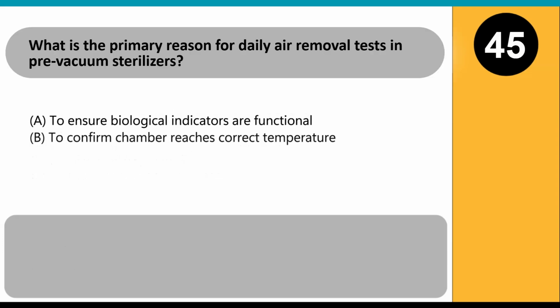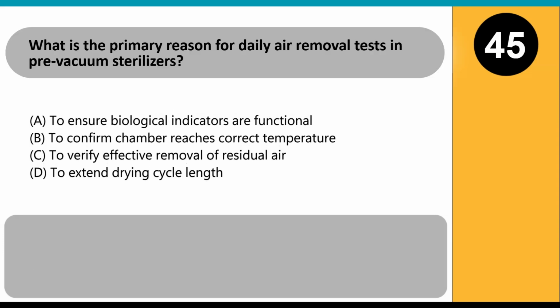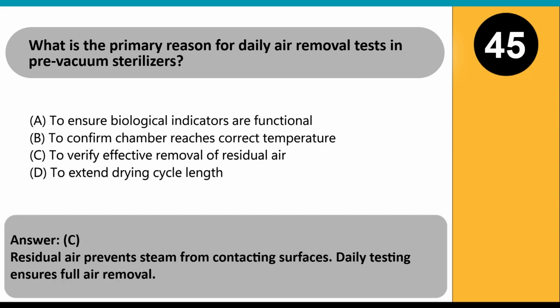What is the primary reason for daily air removal tests in pre-vacuum sterilizers? A. To ensure biological indicators are functional. B. To confirm chamber reaches correct temperature. C. To verify effective removal of residual air. D. To extend drying cycle length. Answer: C. Residual air prevents steam from contacting surfaces. Daily testing ensures full air removal.